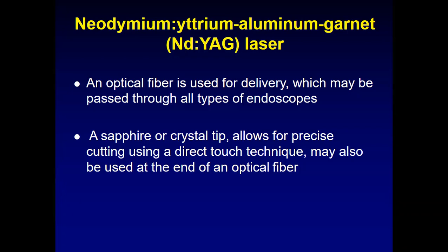So the tip of the laser fiber has to be outside the ureteroscope or any instrument which you are using. It has got a sapphire or crystal tip which allows precise cutting using a direct touch technique, and may also be used at the end of an optical fiber. What is a direct touch technique?